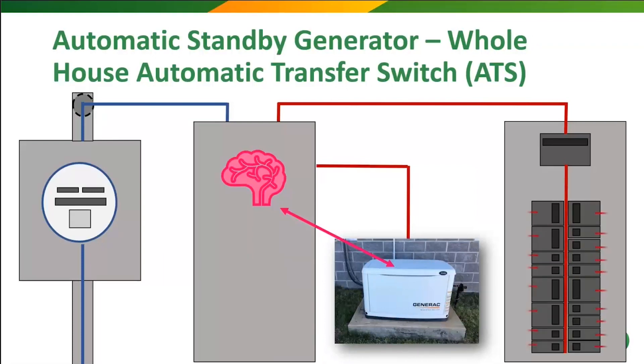Now, remember, this is a super smart switch, and it doesn't just open the floodgates for all of the power-hungry systems to go demanding power right away. Through a series of controllers and modules, it prioritizes those loads to give you what you need. Then, once the demand for those needed items subsides, it allows the other major systems to turn on. All this is set up in advance, and you don't have to do anything manually. This is truly automatic.